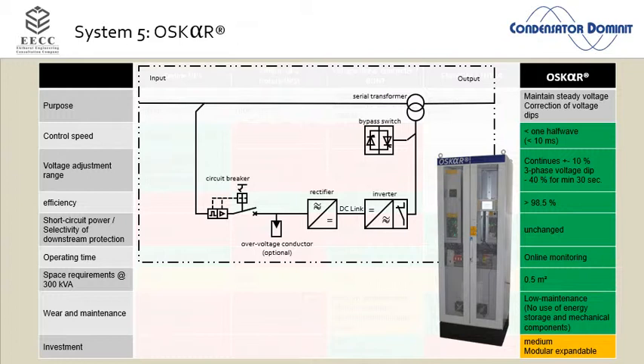You get a short circuit between the 110 kilovolt or 220 kilovolt line and the mast, not between the two lines. So one phase against earth is missing. Now we have a lot of transformers stepping down from high voltage to medium to low voltage, and each time the missing phase gets diluted a bit. So what we often see is: if one phase is missing on the high voltage side, we get a voltage sag on the medium or low voltage side that's an average across the three phases, about 30%. One phase might be down 50%, another 40%, another only 20%, but on average the typical voltage sag we see is 30-40%.